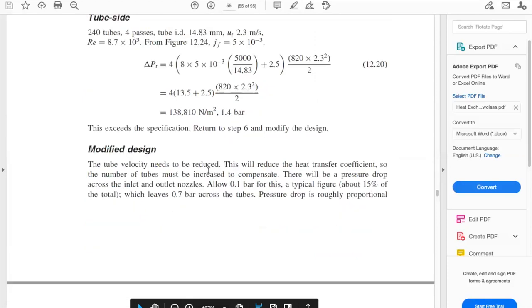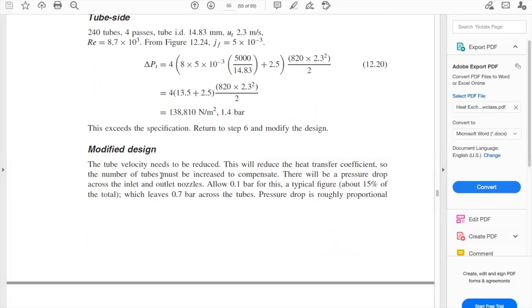Let's modify the design. The tube velocity needs to be reduced because it impacts directly the delta P. Reducing velocity will reduce the heat transfer coefficient, so the number of tubes must be increased to compensate. There will be a pressure drop across the inlet and outlet nozzles, so allow 0.1 bar for this — a typical figure of about 15% of the total. Multiplying 0.8 bars by 0.15 gives around 0.12, leaving around 0.7 bars across the tubes.